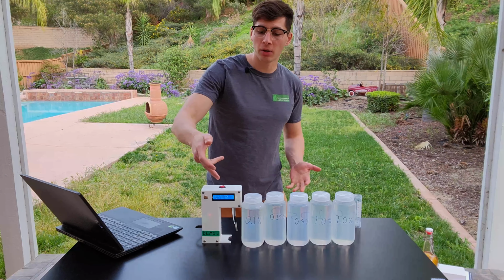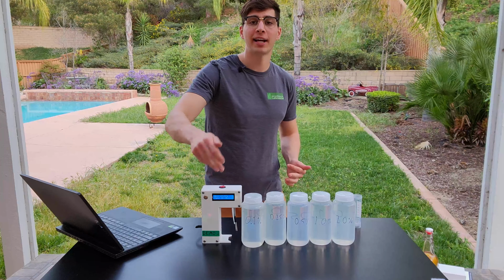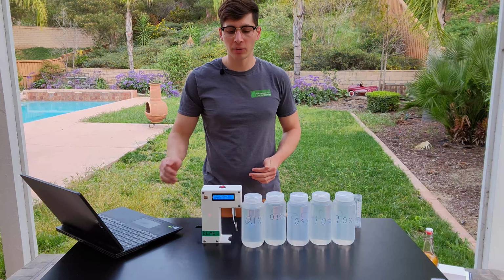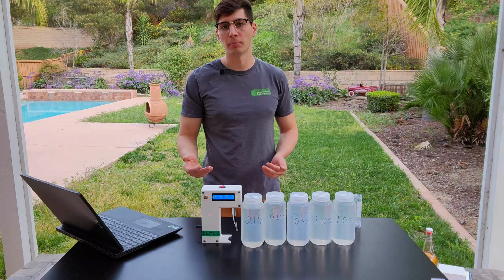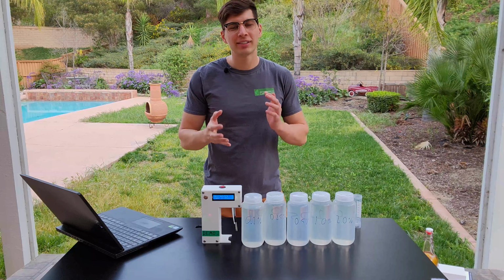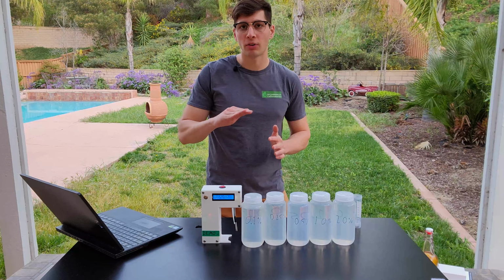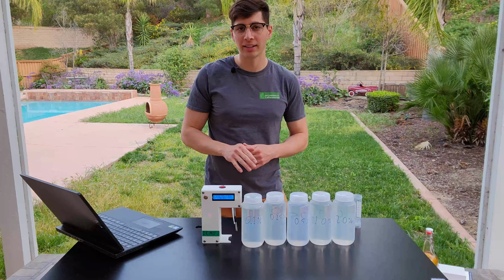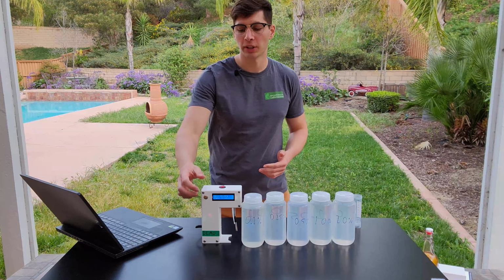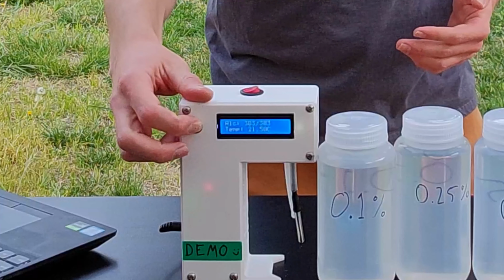So now the readings on the left of the detector should very rapidly fall down, and the reading on the right should stay the same. It takes about 30 seconds to a minute for the readings to fall back down to sort of a baseline level, and once that happens, you can press and hold the red button to reset.